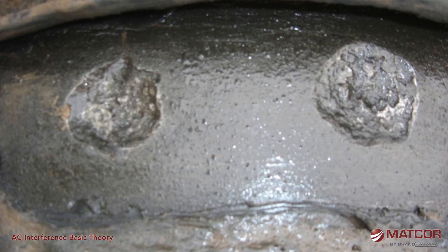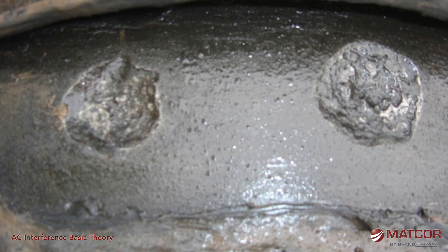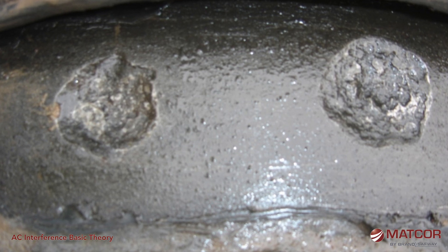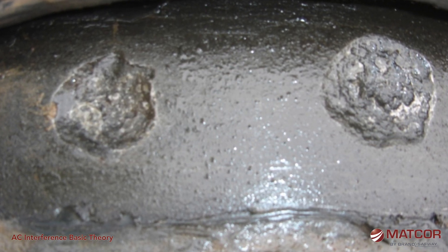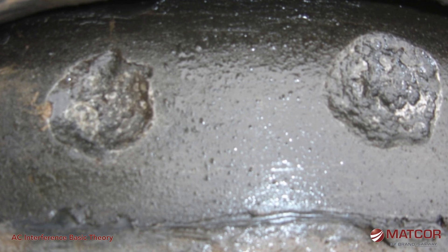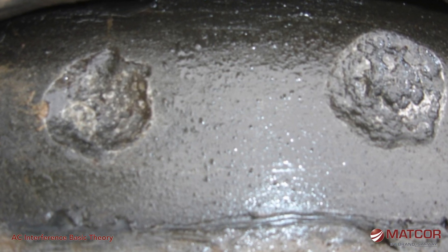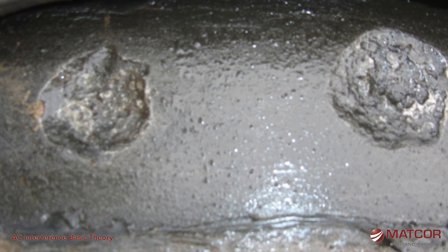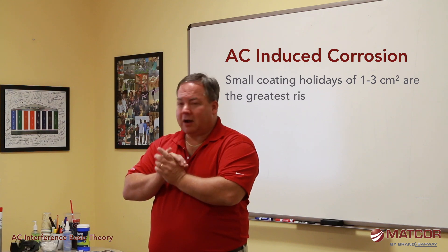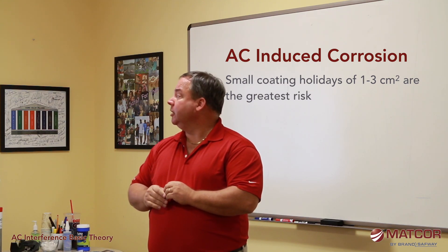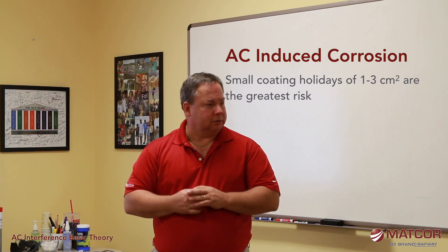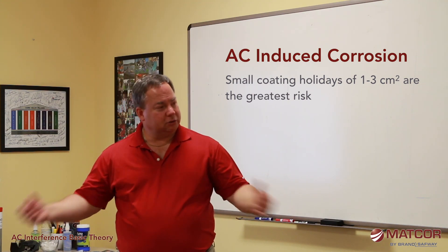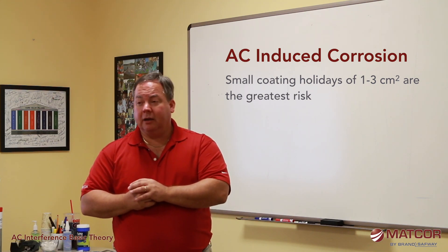This is what AC induced corrosion looks like — it can be round craters, sometimes very deep, and may even look like microbiologically induced corrosion because they have similar characteristics. It occurs in the presence of AC transmission lines, sometimes distribution lines, and typically in a low soil resistivity environment. Testing has found that the optimum coating holiday size for high AC corrosion is between one and three centimeters squared.